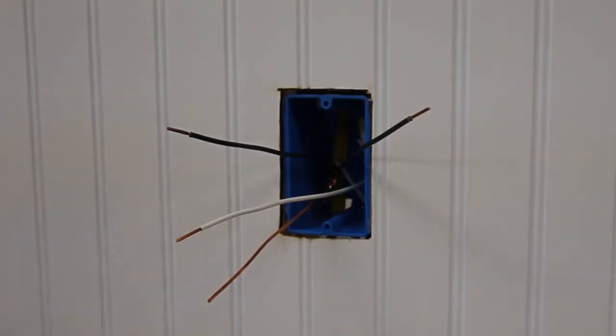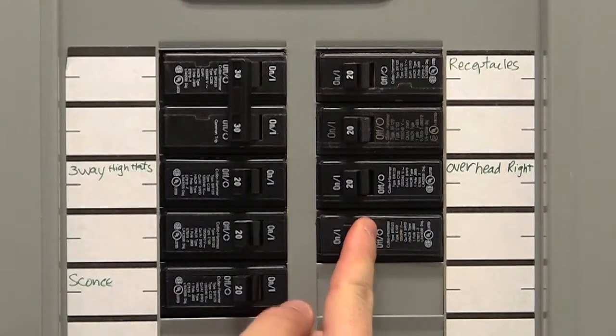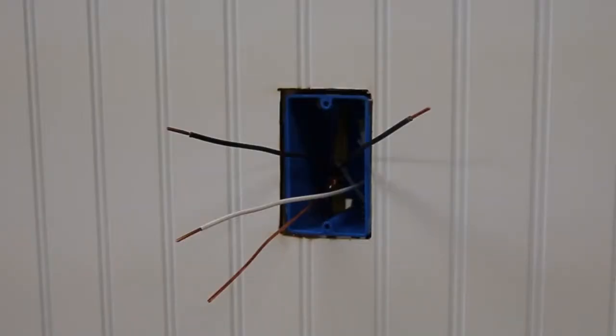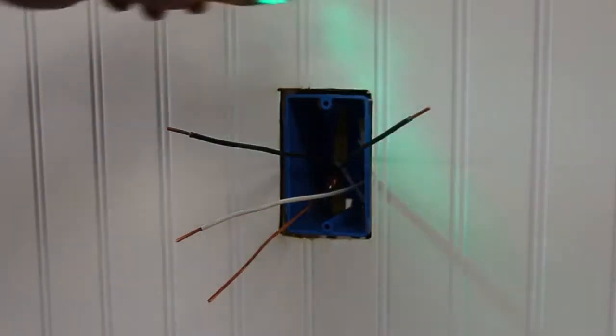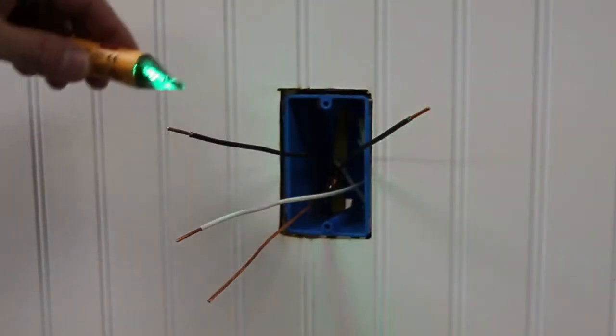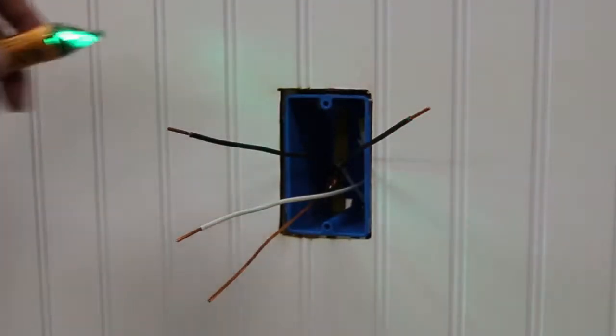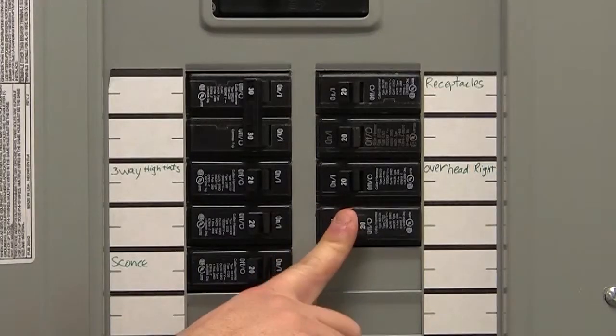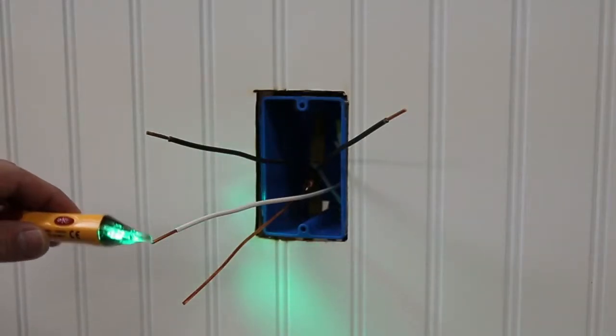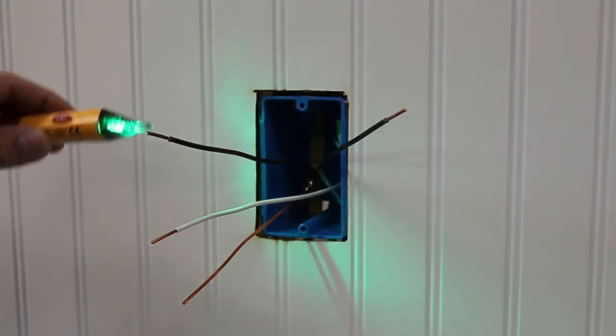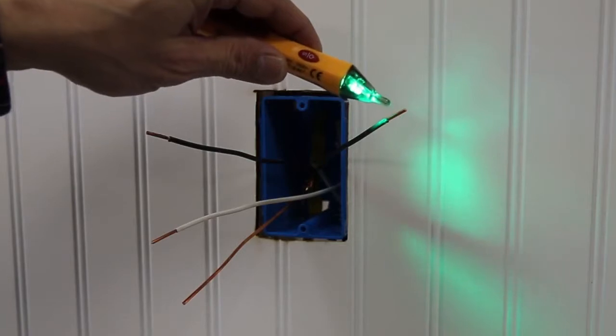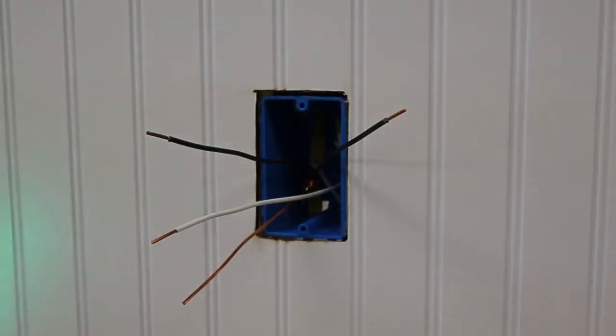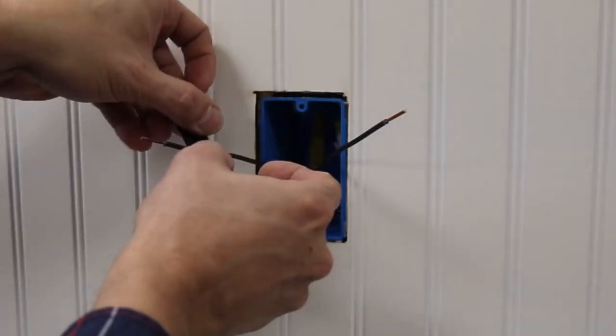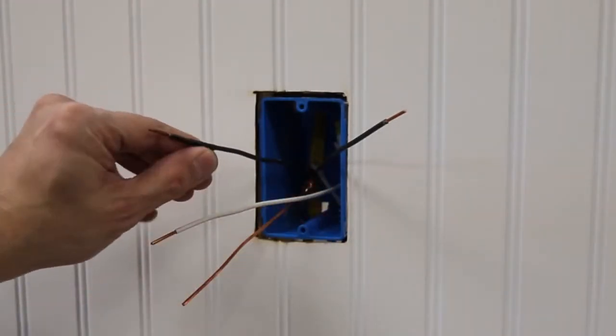To do this, turn the circuit breaker back on. Carefully use the voltage tester to test each wire. The hot wire will be indicated by the tester. Once identified, turn off the circuit breaker to shut power and test to ensure that the power is off. Use a small piece of electrical tape to label the hot wire. Identify whether the wiring application is single pole or a three-way application. If wiring in the box does not resemble either of these configurations, please consult an electrician.